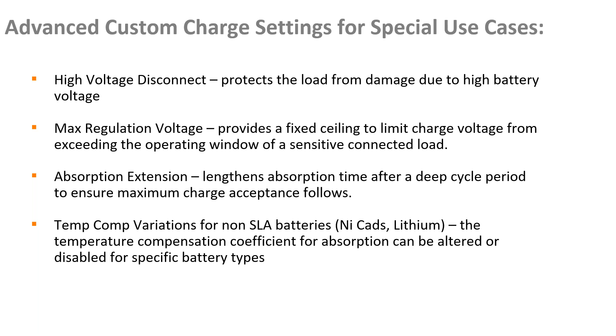And then, of course, being able to calibrate your temperature compensation coefficients and temperature range is nice to have as well. Again, with lithium, it's not as much needed. You're not compensating the charging output in different temperatures. But for lead acid, where you do have some elasticity in the behavior, you want to be able to dial in that charging regulation as much as possible so that it's accurate throughout the temperature range specified. And you have full custom programmability within MSView to do that.